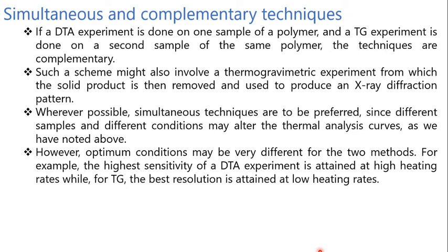While in the case where we have used the TGA and DTA experiments at the same time on the same sample, we can call it a simultaneous technique. Such a scheme might also involve a thermogravimetric experiment from which the solid product is then removed and used to produce the X-ray diffraction pattern. Wherever possible, simultaneous techniques are to be preferred, since different samples and different conditions may alter the thermal analysis curve, as we have noted. However, optimum conditions may be very different for the two different methods.